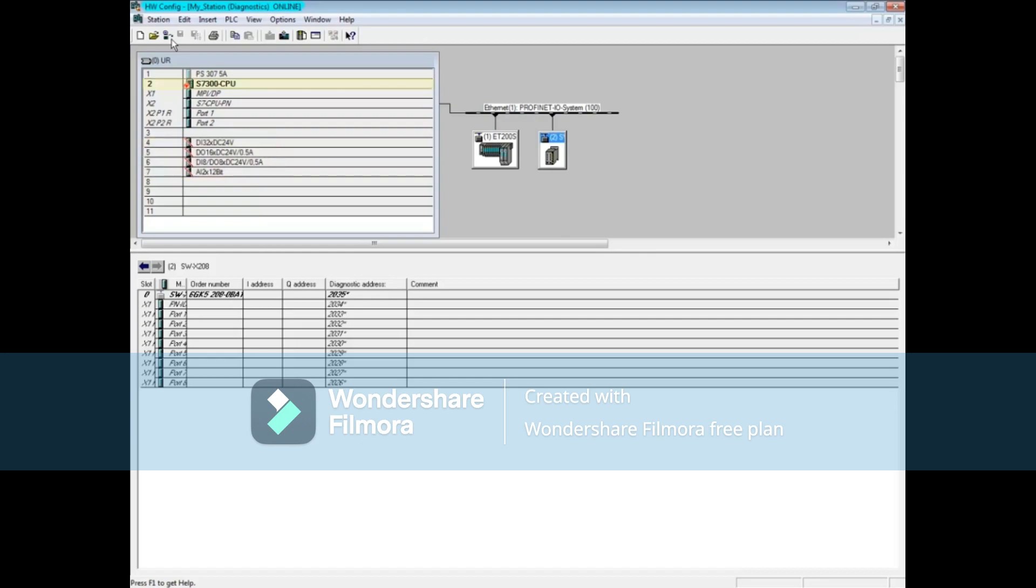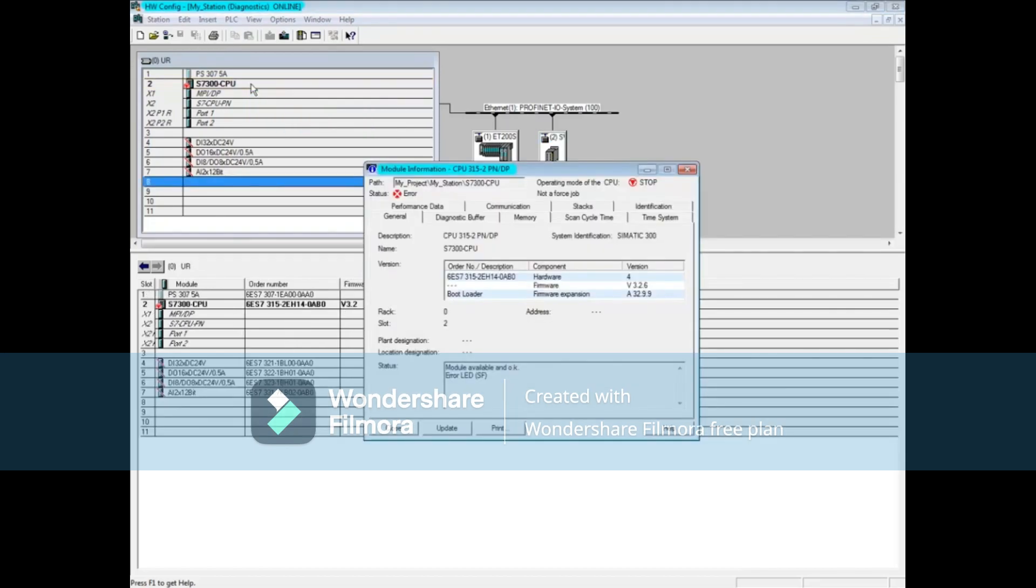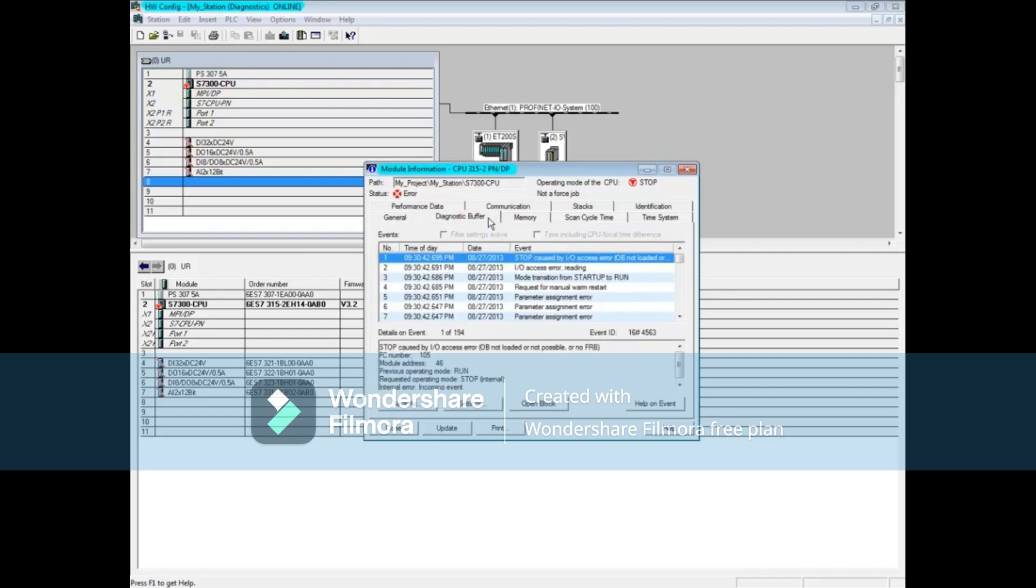While online, double-click on the CPU to open the module information tool. Click on the diagnostic buffer tab. The first message says that a stop has occurred because of an I.O. access error. FC 105 was attempting to access I.O. Internal error means the code initiated the access.